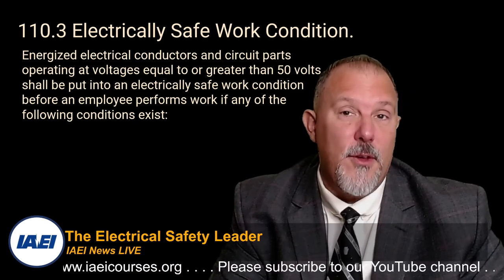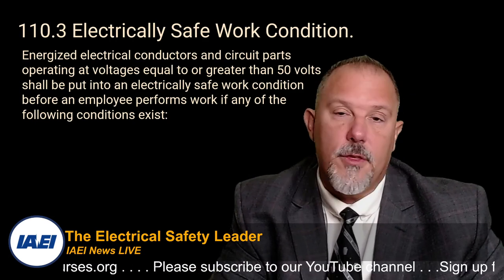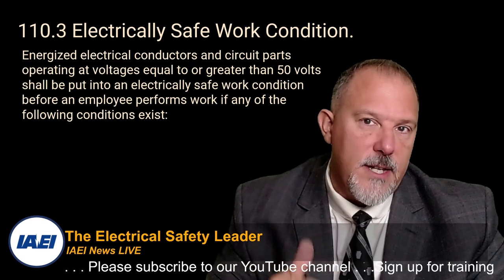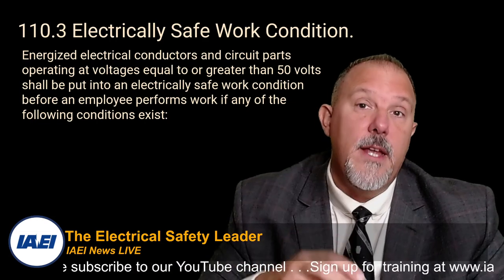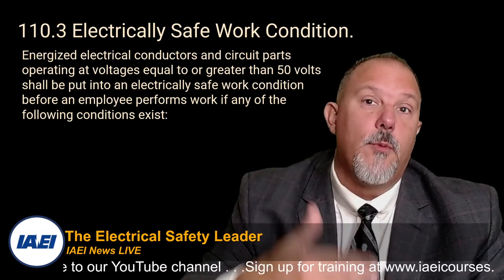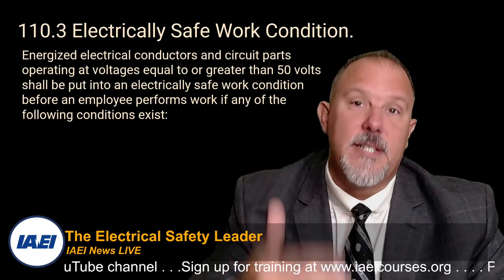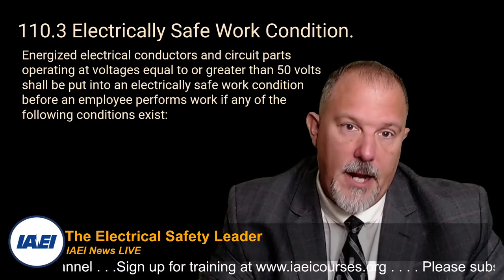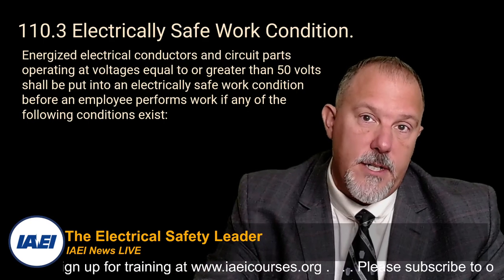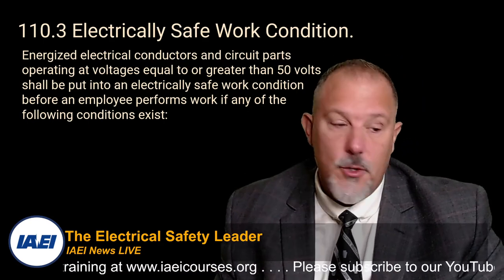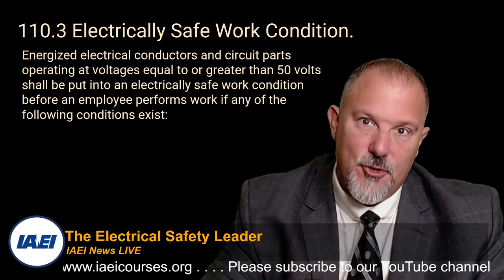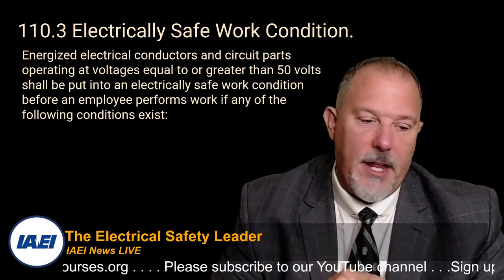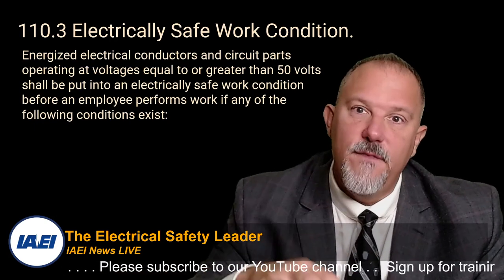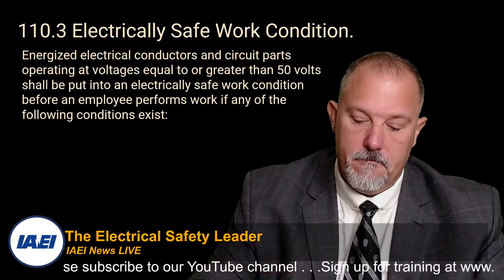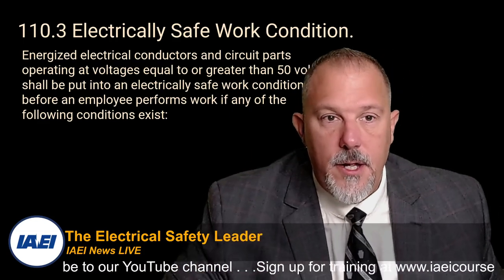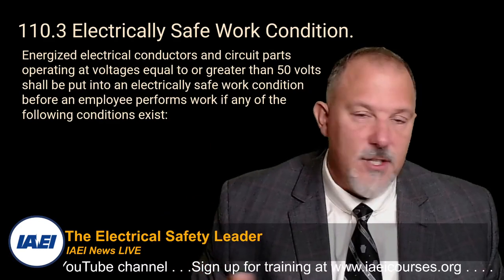3 foot 6 inches. Remember those, 3.5 feet. You're 3.5 feet from an exposed energized conductor. If you're inside that boundary, you are within the shock protection boundary, and you need to establish an electrically safe work condition, or what else? Once you're in that boundary, now you're in Article 130 and all of the requirements around work involving the electrical hazard. So now remember, this is not arc flash. This is not your arc flash boundary.